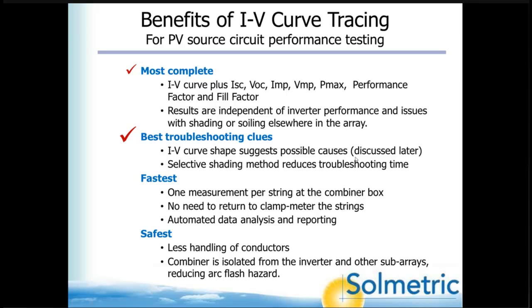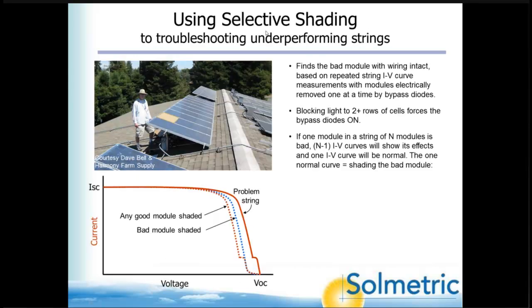The IV curve shape suggests possible causes, which we'll discuss later, and the selective shading method reduces troubleshooting time. And I'm going to show you just one slide on that. Selective shading is used to find the bad module in a string of modules without the requirement for actually disconnecting the modules from one another and testing them separately. So the way it works is you use a piece of cardboard or black rubber or something to switch on all the bypass diodes in a module, and you measure the string again. And if the problem module is the one that you put the cardboard over, then you will electrically bypass it and eliminate the problem from the string.